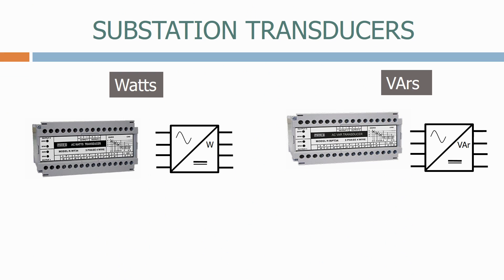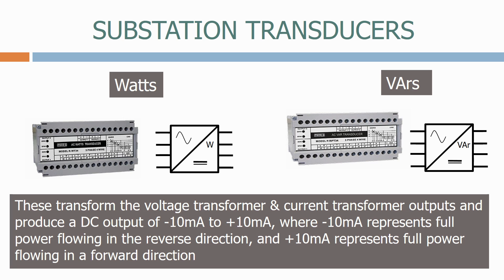Finally, we have a watts transducer and vars transducer. These transform the voltage transformer and current transformer outputs, and produce a DC output of -10mA to +10mA, where -10mA represents full power flowing in the reverse direction, and +10mA represents full power flowing in the forward direction.